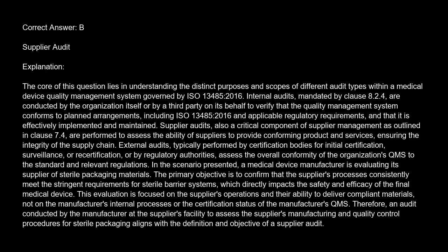13485:2016. Internal audits, mandated by Clause 8.2.4, are conducted by the organization itself or by a third party on its behalf to verify that the quality management system conforms to planned arrangements, including ISO 13485:2016 and applicable regulatory requirements, and that it is effectively implemented and maintained.